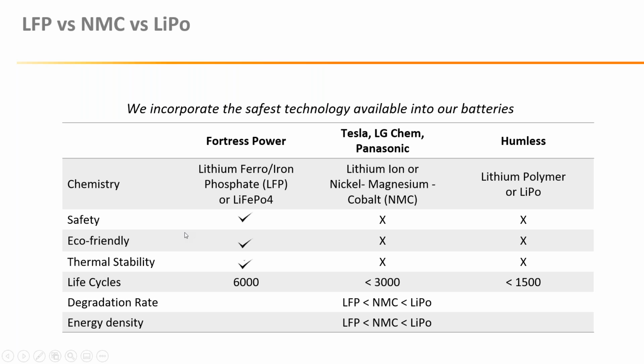For something like a stationary application where you want a lot of cycles, because you'll be cycling it every day to power different electrical loads, this is where we see the benefit of the phosphate chemistry. The degradation rate of phosphate is less than that of the cobalt chemistry and less than that of the polymer chemistry. It's not as energy dense as the cobalt or the polymer, but that is the trade-off — not as energy dense, but more safe.